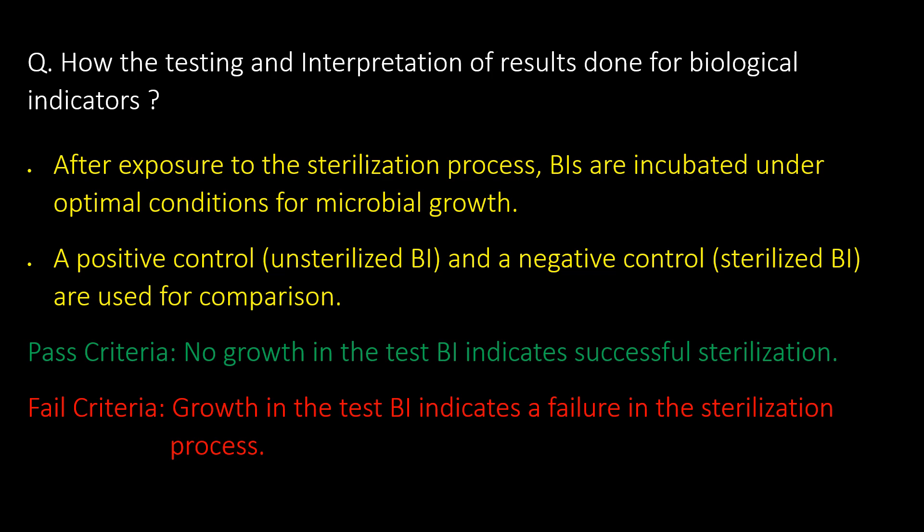Very important question: how is the testing and interpretation of results done for biological indicators? After exposure to the sterilization process, biological indicators are incubated under optimal conditions for microbial growth. A positive control (unsterilized biological indicator) and a negative control (sterilized biological indicator) are used for comparison. Pass criteria: no growth in the test biological indicator indicates successful sterilization. Fail criteria: growth in the test biological indicator indicates a failure in the sterilization process.